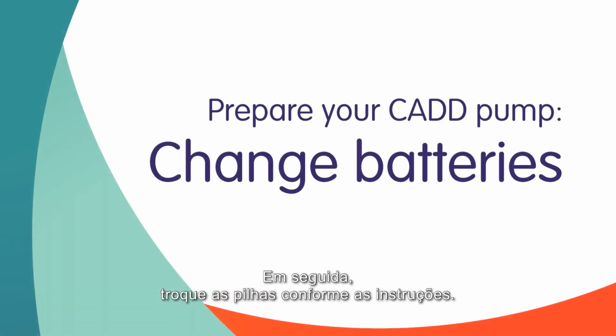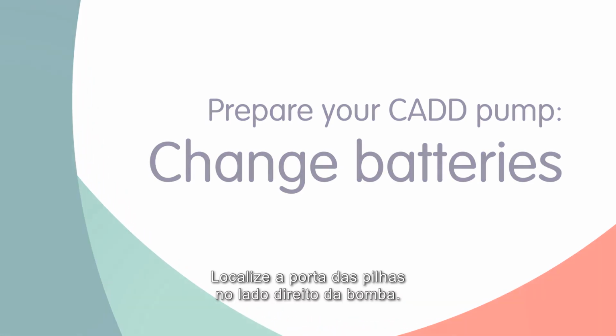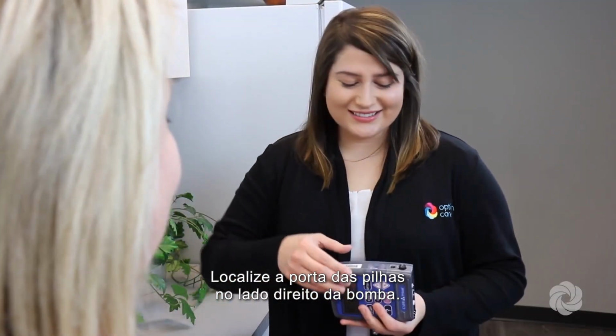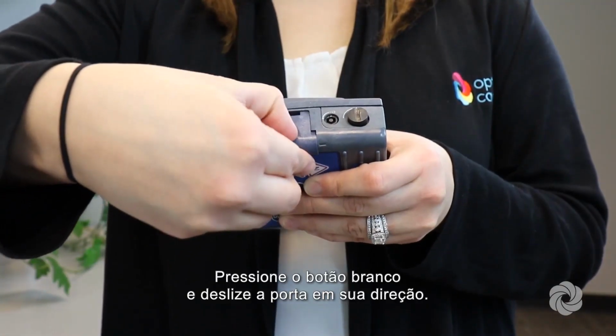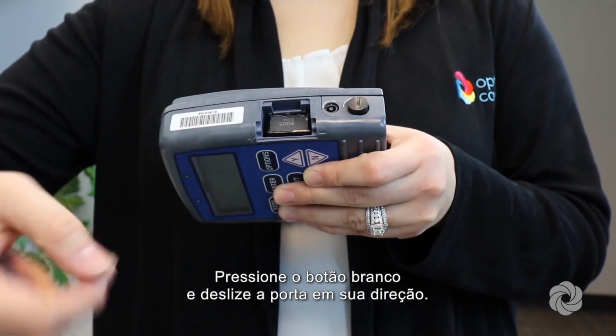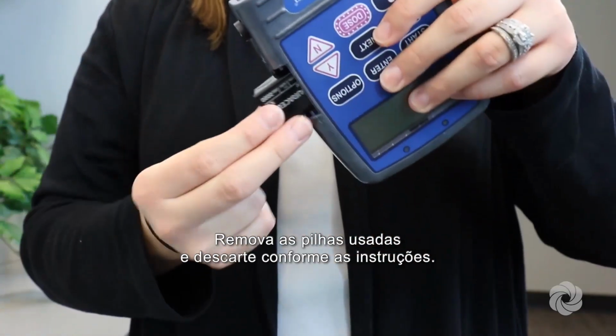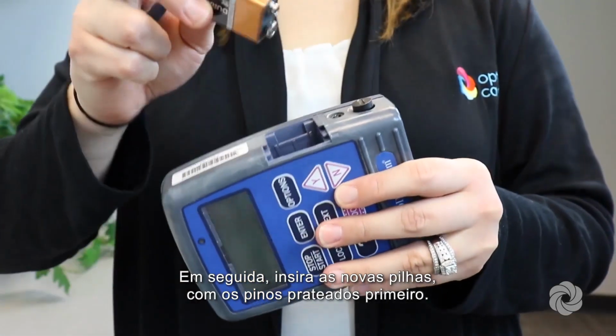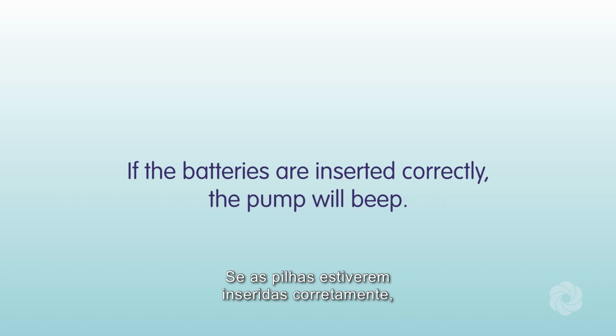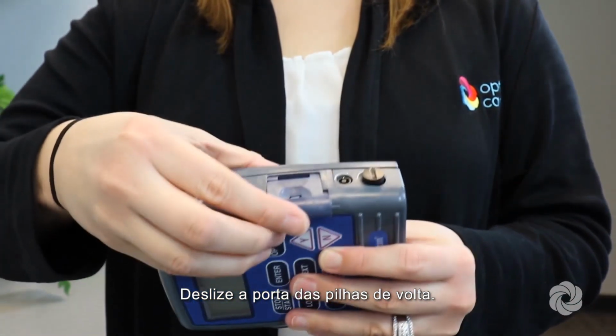Next, change the batteries as directed. Locate the battery door on the right side of the pump. Press the white button and slide the door towards you. Remove the used batteries and discard as instructed. Then, insert the new batteries, silver prongs first. If the batteries are inserted correctly, the pump will beep. Slide the battery door back on.